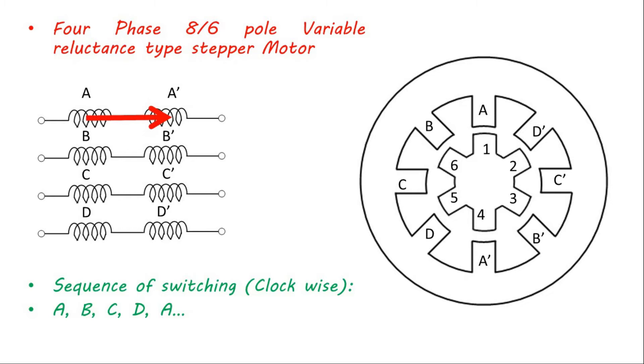When phase A is switched on, the equilibrium position of the rotor is shown here. In this position, flux travels through a minimum reluctance path using rotor pole 1 and 4. This is a stable position of the rotor.